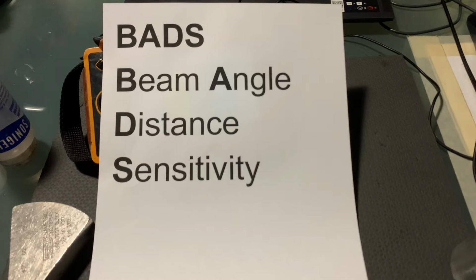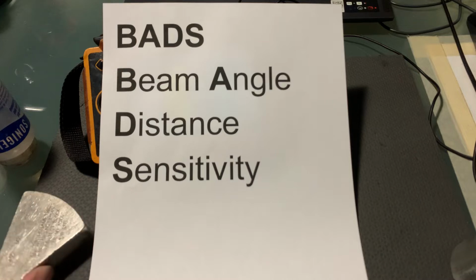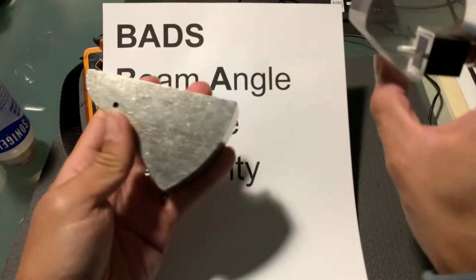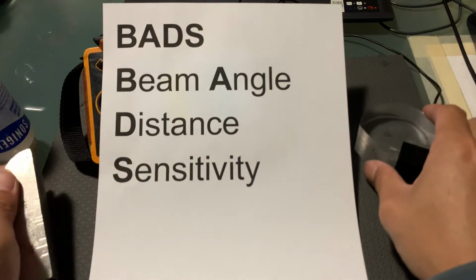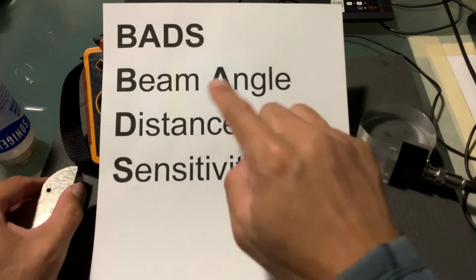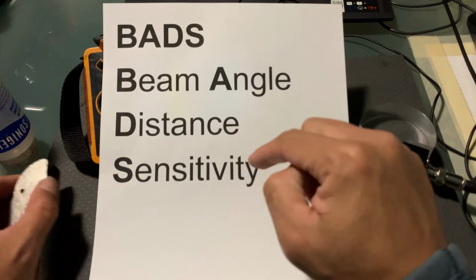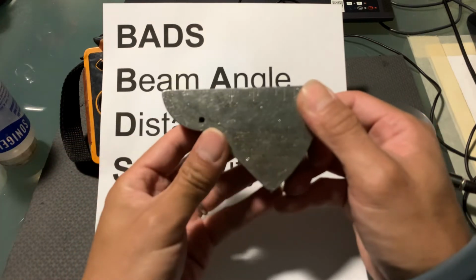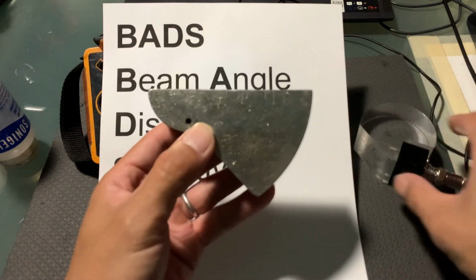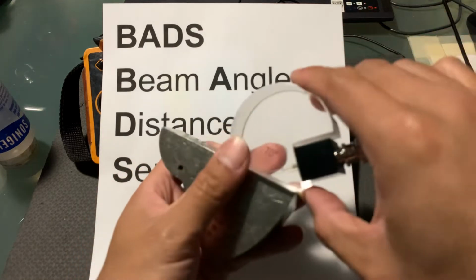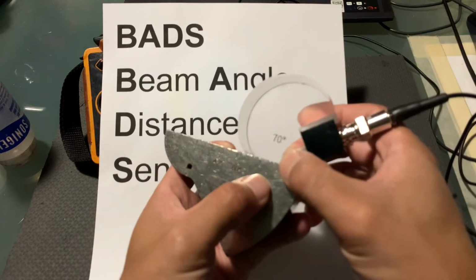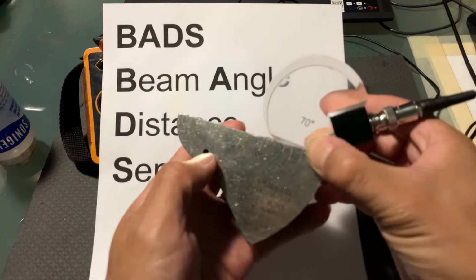I'm going to show you how to calibrate a flaw detector machine using a DSC block and a 70-degree wedge. We'll be using the acronym BADS: beam angle, distance, and sensitivity. Beam angle will be done from putting our wedge and lining up the mark with the beam exits on the wedge to the 70-degree mark to shoot for the side drill hole.